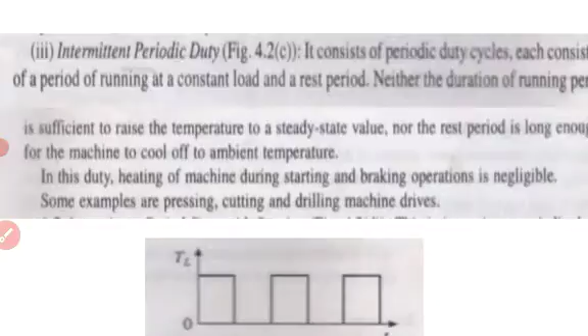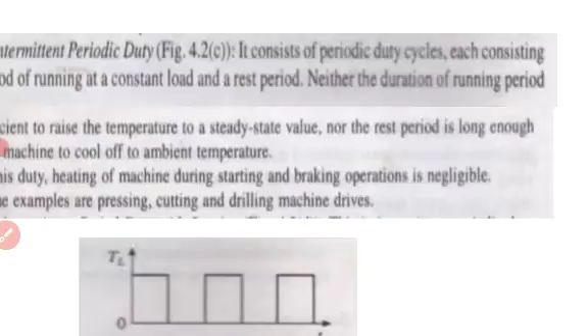Next one is intermittent periodic duty. It consists of periodic duty cycles, each consisting of a period of running at a constant load and a rest period. Neither is the duration of the running period sufficient to raise the temperature to a steady state value, nor is the rest period long enough for the machine to cool off to ambient temperature. Earlier, in the short time duty, we allowed it to cool down to ambient temperature. In this category, intermittent periodic duty, it is not enough to reach the steady state temperature.